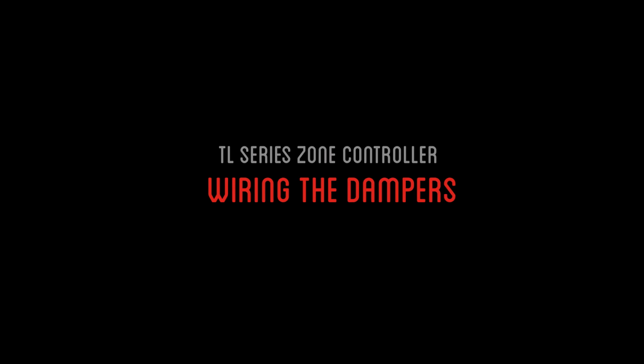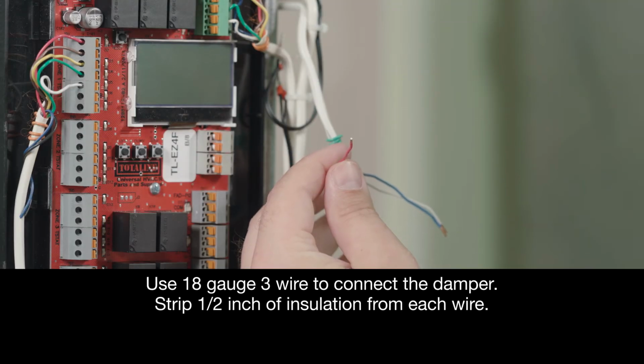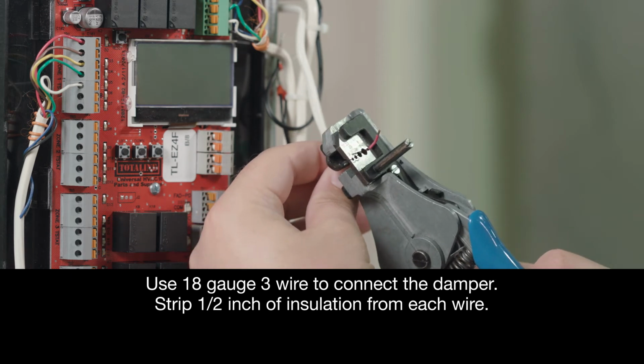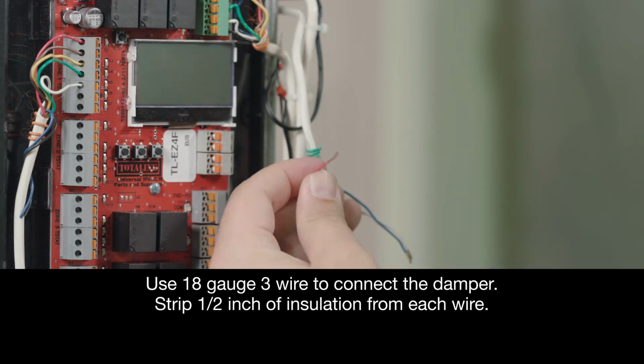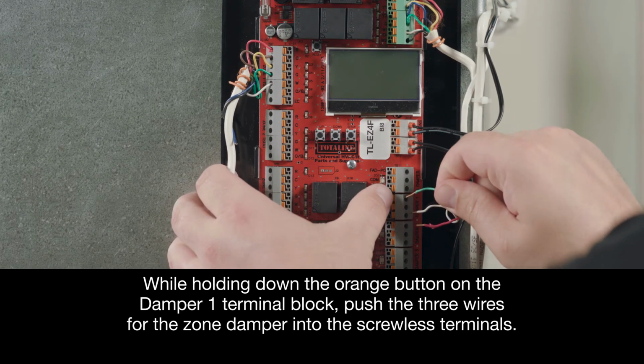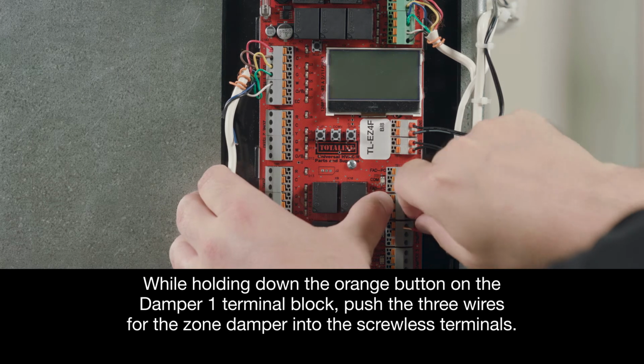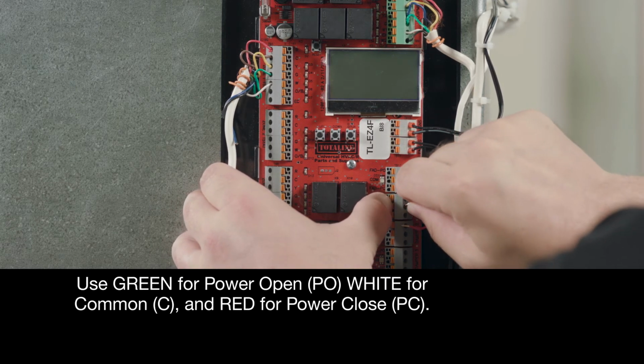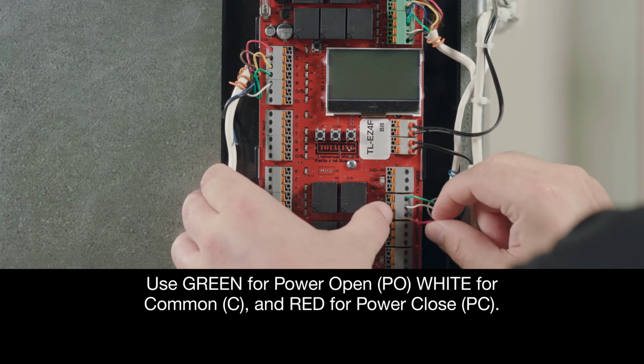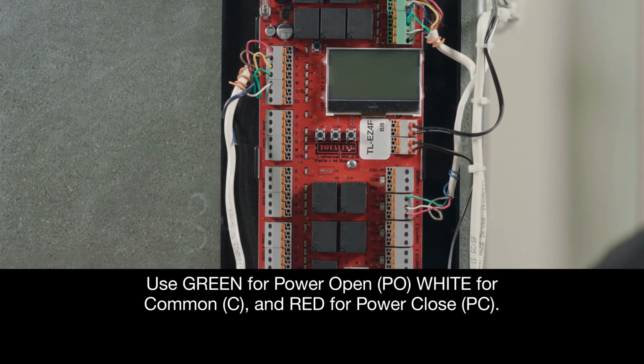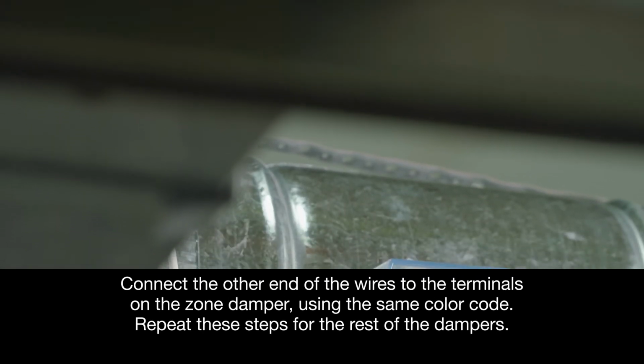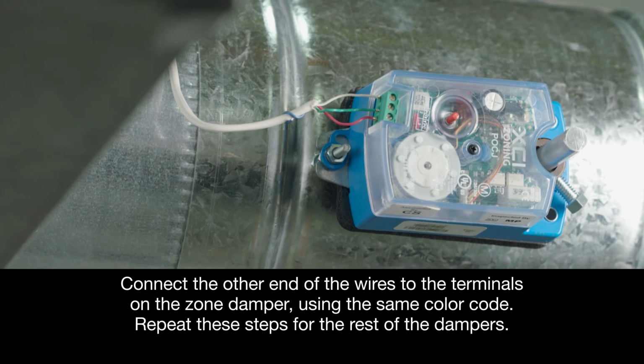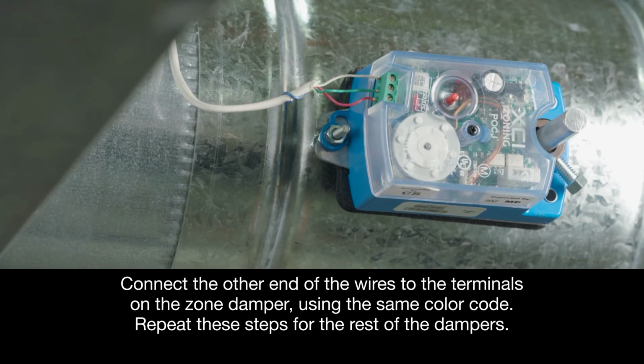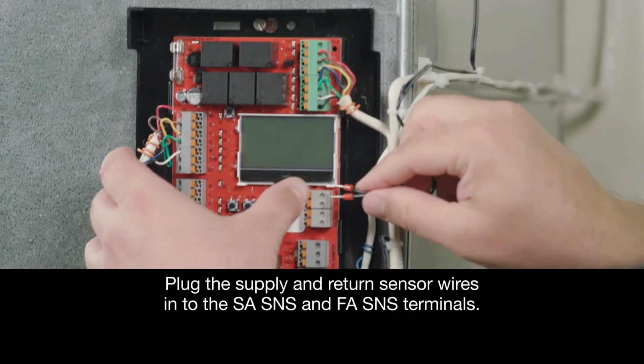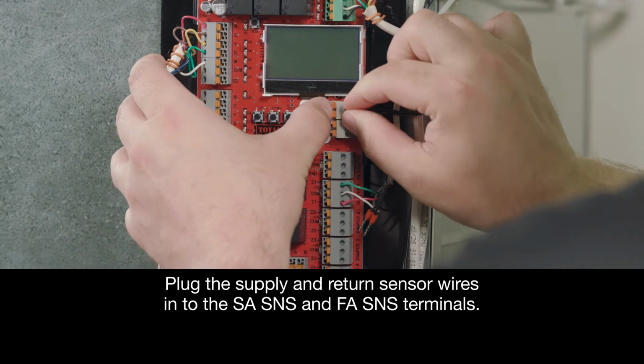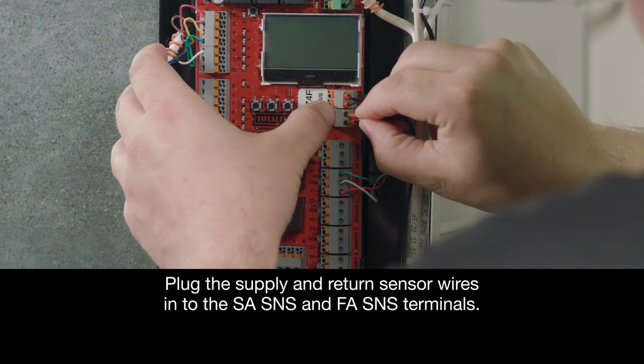Now let's move on to wiring the power open, power close 3-wire dampers. We'll use 18-gauge 3-wire to connect the damper. First, we'll strip a 1/2 inch of insulation from each wire. Then, while holding down the orange button on the damper 1 terminal block, push the 3 wires for the zone damper into the screwless terminals. Use green for power open, or PO, white for common, or C, and red for power close, PC. Connect the other end of the wires to the terminals on the zone damper using the same color code. Then, repeat these steps for the rest of the dampers. Next, plug the supply and return sensor wires into the SA SNS and FA SNS terminals.